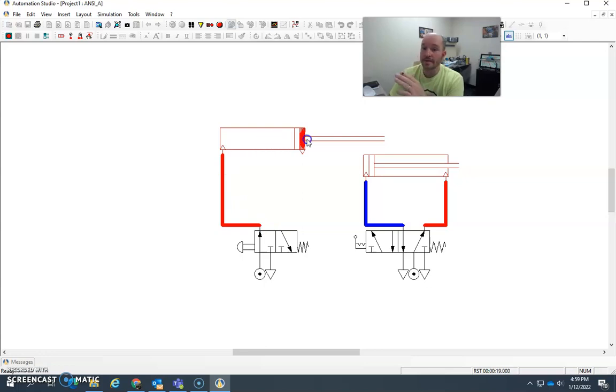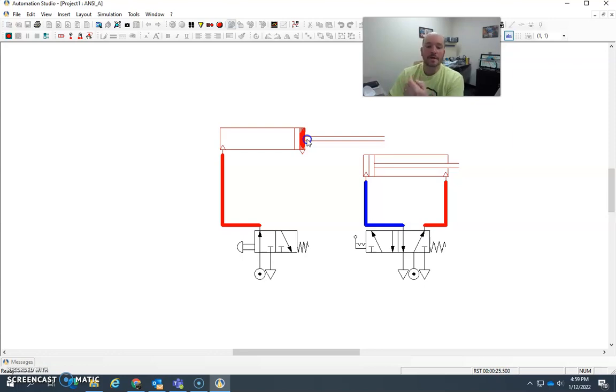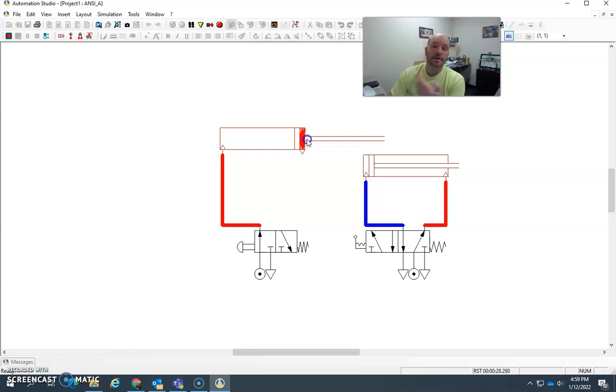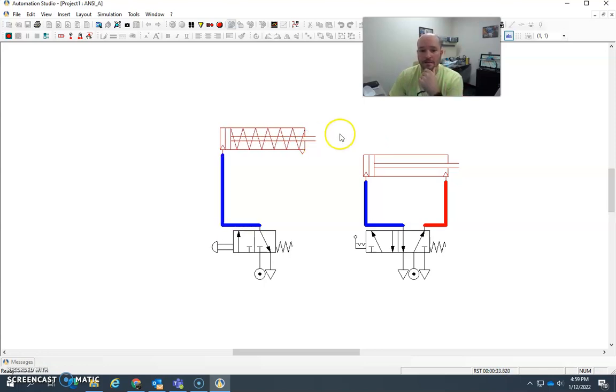Now, in this case, this is a spring return cylinder, pretty common in a lot of light pneumatic work. They're very, very useful because they don't require an action to retract them, like a pneumatic action or an electrical action. Springs will do it automatically.